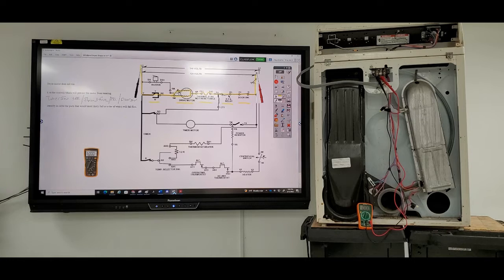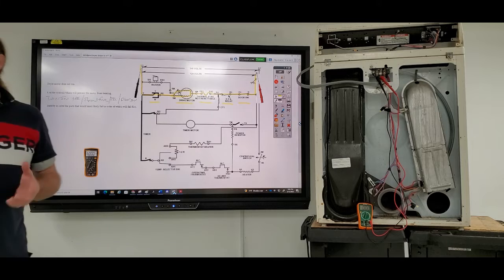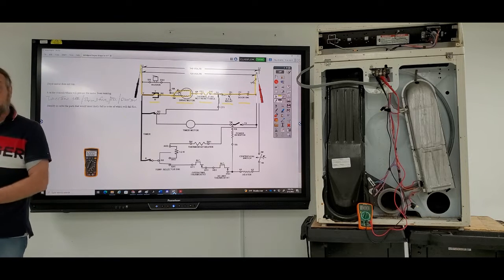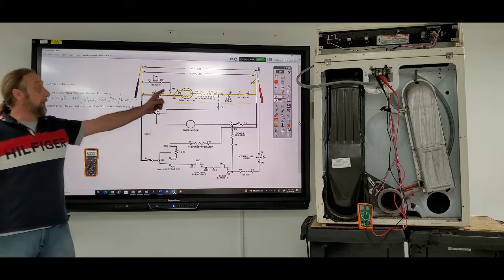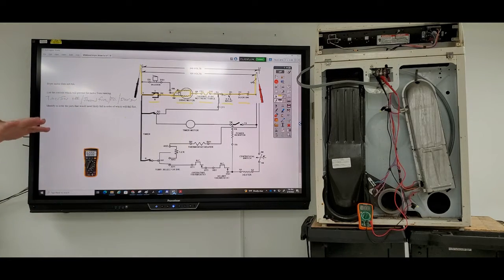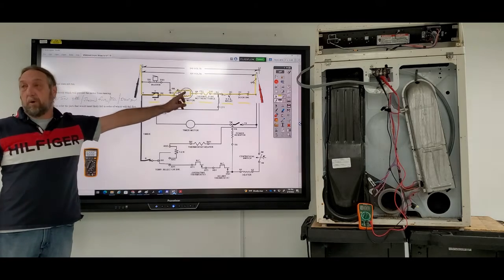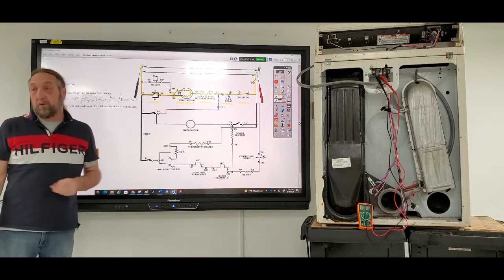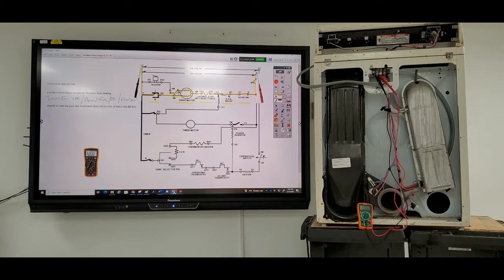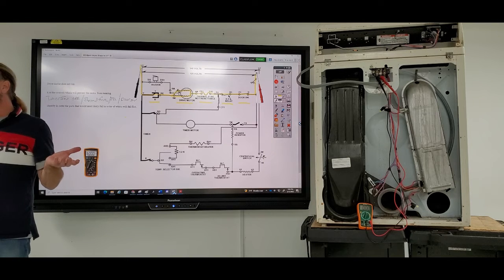How many switches or controls are in series with that motor? 4. Now we could have added the centrifugal switch in the motor, but the motor would at least hum. If I hear the motor humming and not running, I wouldn't worry about any of the things I just listed, because if any of them are bad, the motor's not even going to hum. So if it hums, the problem's either one of my 2 windings in the motor is at fault or the centrifugal switch is bad. But either way, in order to fix the problem, what's the answer? Replace the motor.